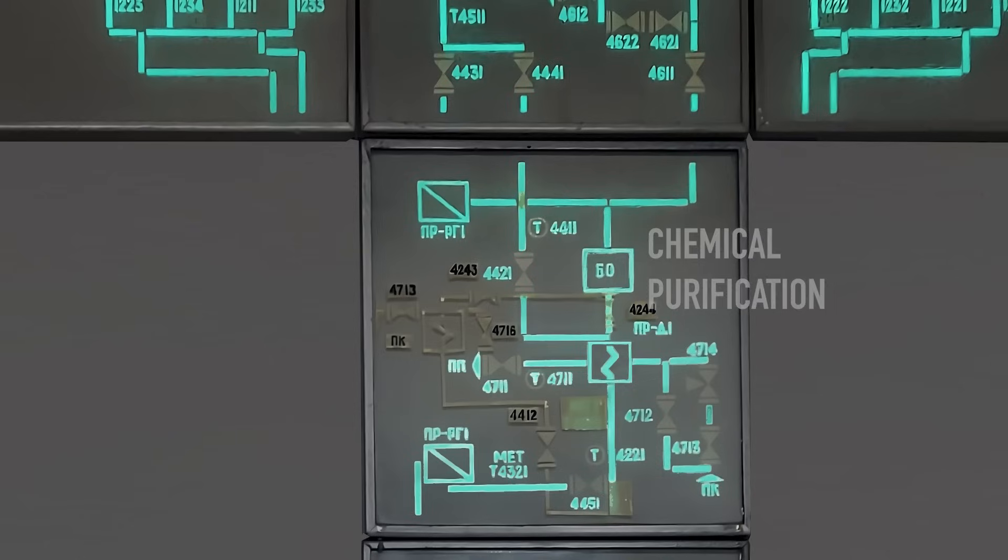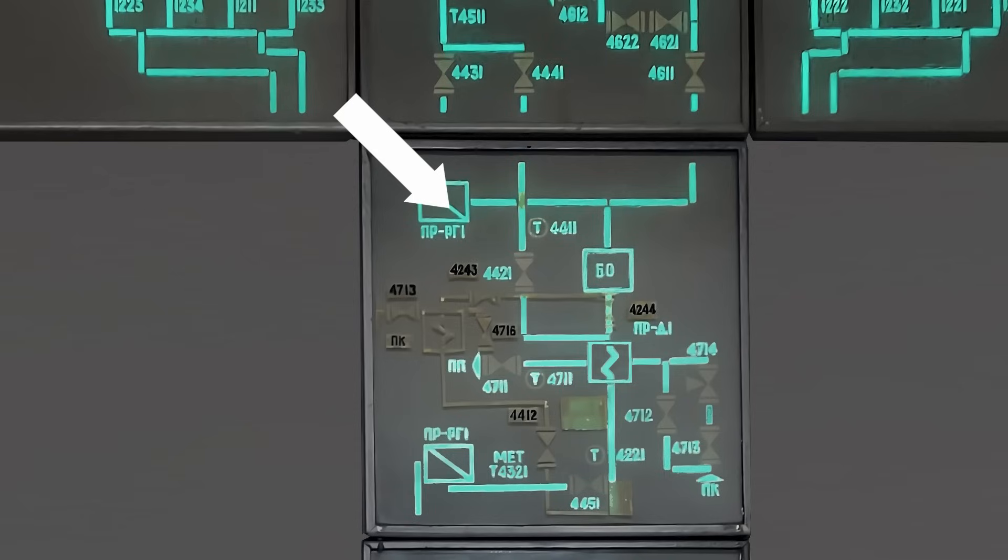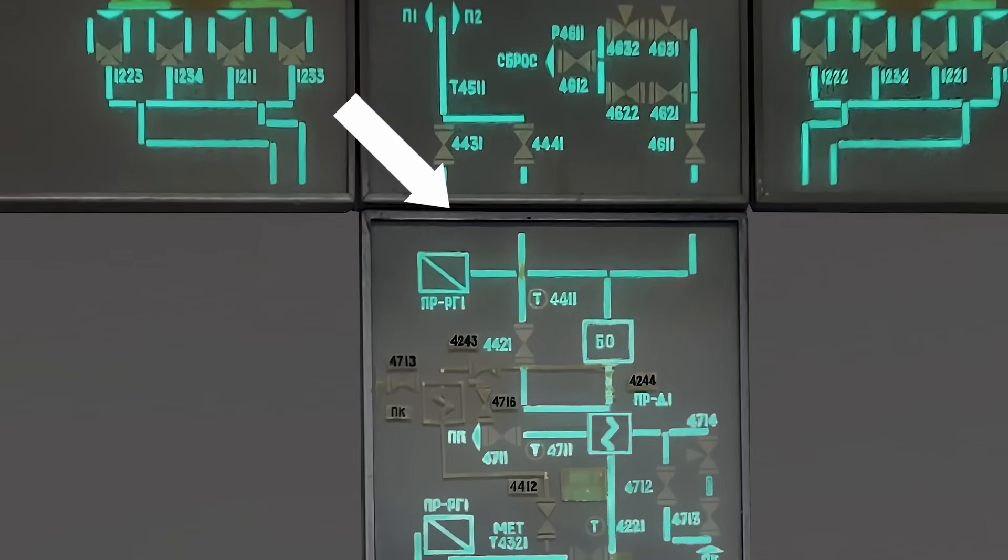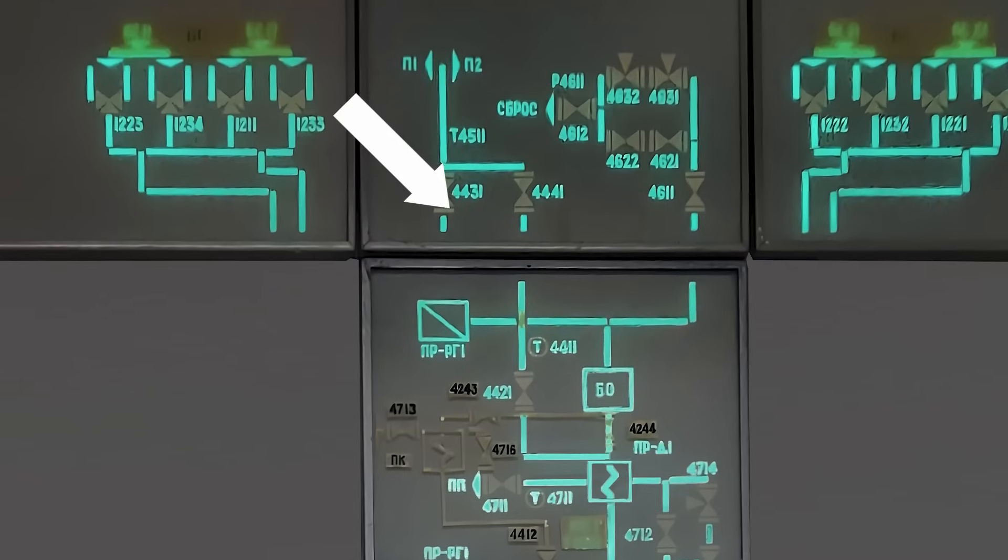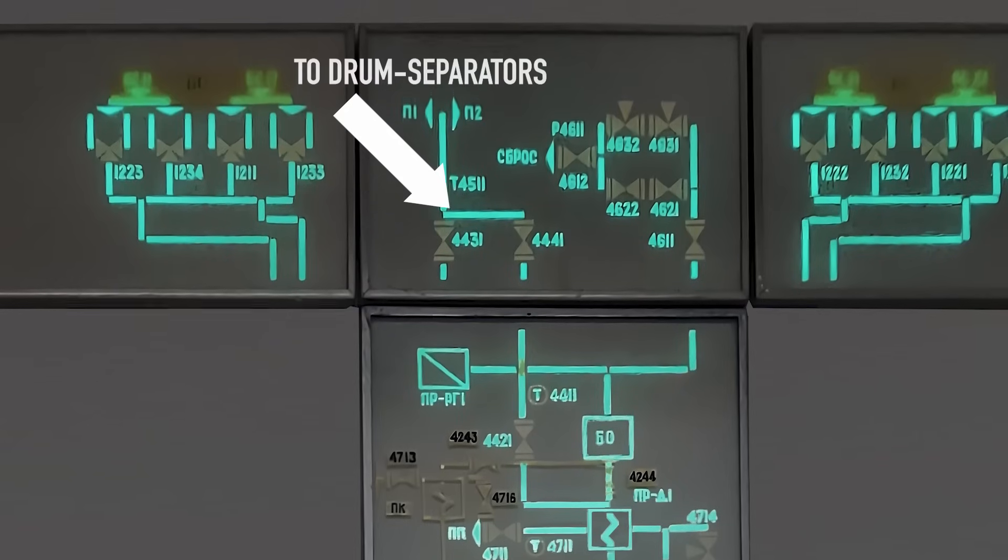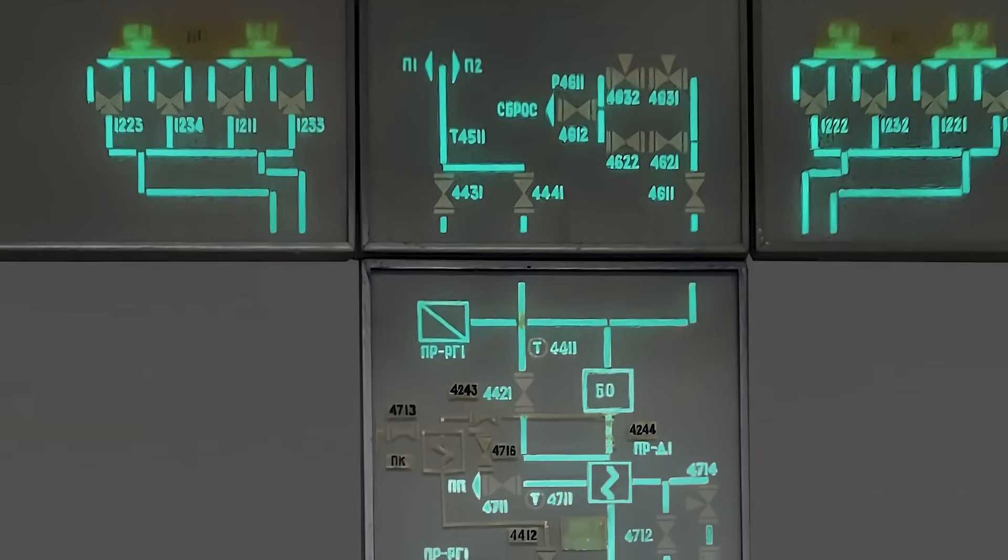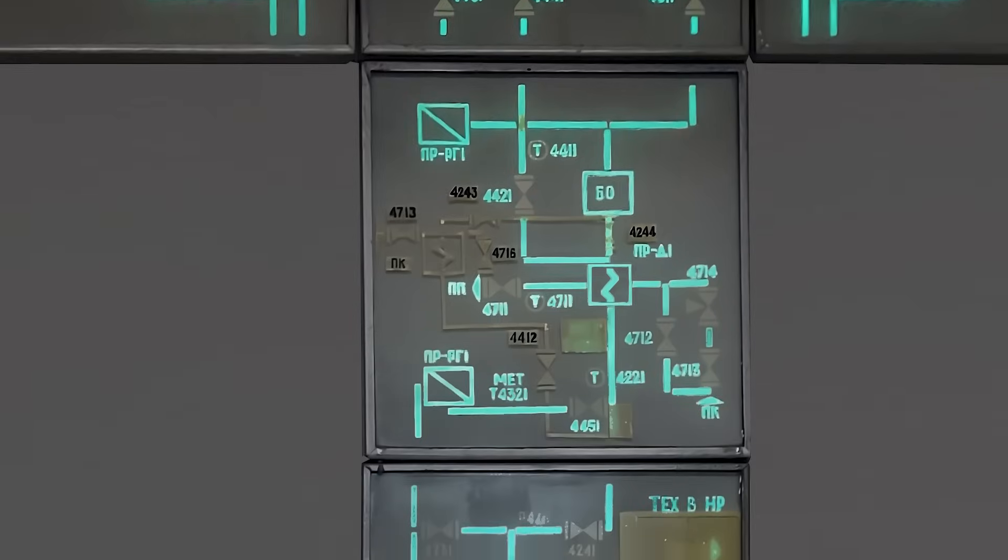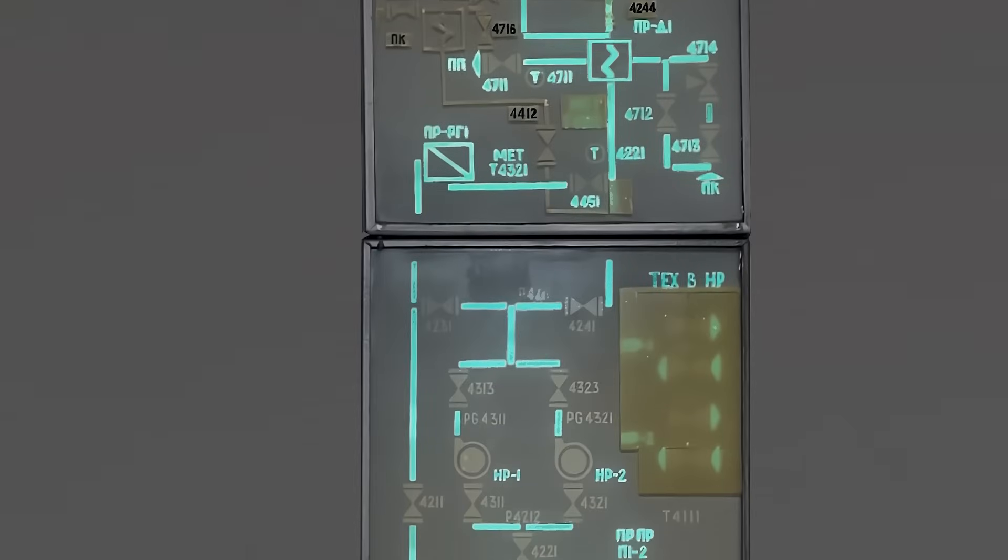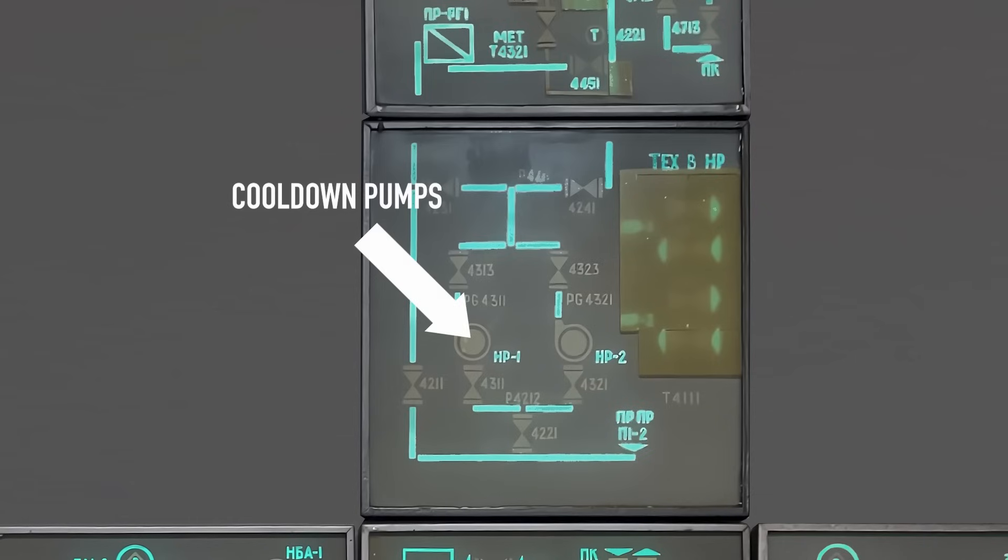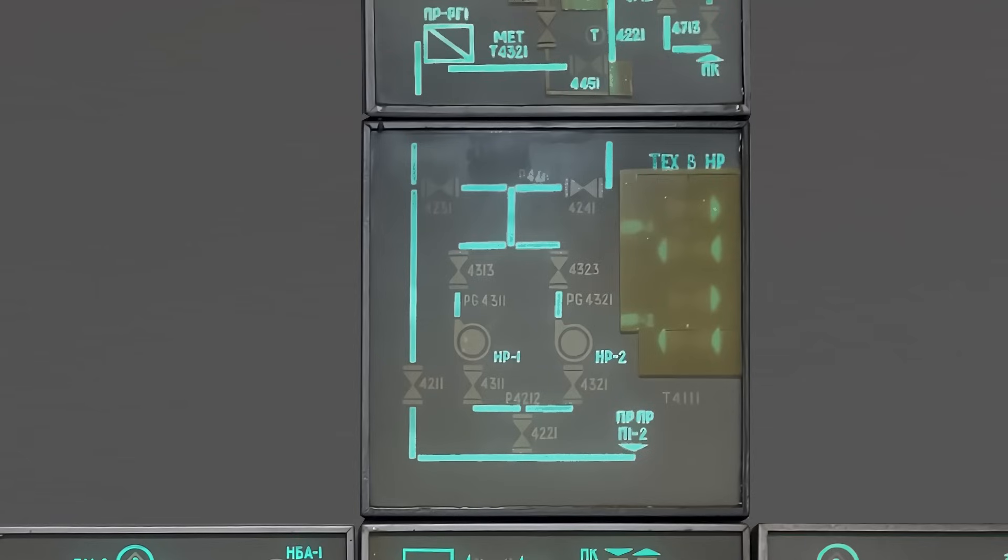But you do not pour cold water into the hot reservoir, right? So before that, once more, it passes through the regenerator to be reheated. And eventually hot water meets hot water. In emergencies or for maintenance, this system also drains excess coolant inside the special tanks using these high power pumps. During the cool-down, the same pumps are used to increase the speed of the blow-down and that basically reduces the temperature inside the drum separators.